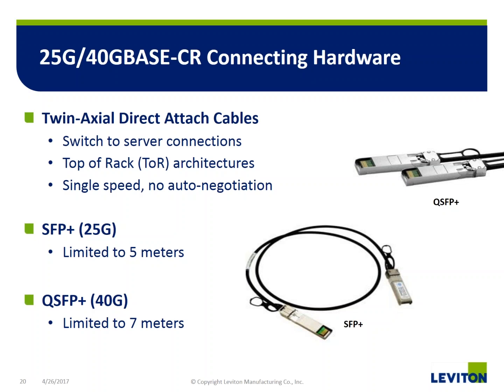Auto negotiation, for those that aren't familiar, is the ability for two pieces of active equipment to have a handshake or conversation and settle on a data rate that works for both. That means a 25G base T switch can also support a 10G base T server, whereas with the twin axial or the optical fiber, that port speed is going to be fixed. It's either 10G, 25G, or 40G. It's not going to be able to talk a different speed.